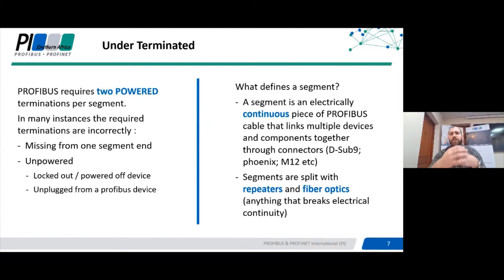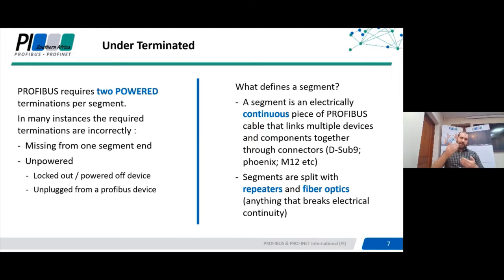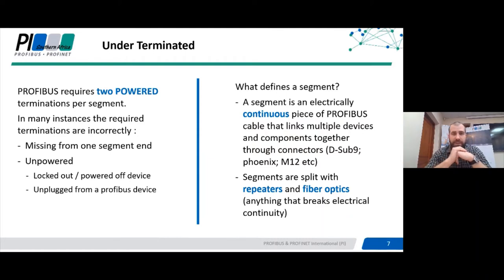One of the most common faults for Profibus DP installations is referred to as under-termination. To understand this, we first need to understand what termination is. A termination is simply a set of resistors or a resistor circuit designed to capture excess energy from the bus once the telegram signal reaches the end of the line. All this energy traveling from a transmitting station will bounce back at the end of the cable and cause reflections, which can interfere with future communications.